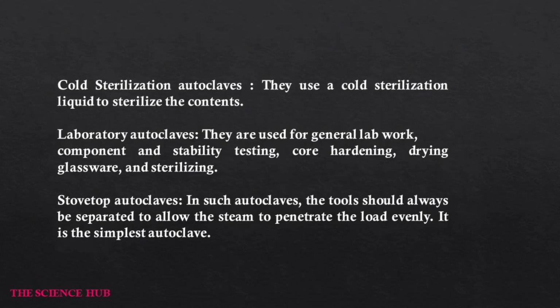Cold sterilization autoclaves. They use a cold sterilization liquid to sterilize the contents. Laboratory autoclaves. They are used for general lab work, component and stability testing, core hardening, drying glassware, and sterilizing. Stovetop autoclave. In such autoclaves, the tools should always be separated to allow the steam to penetrate the load evenly. It is the simplest autoclave.